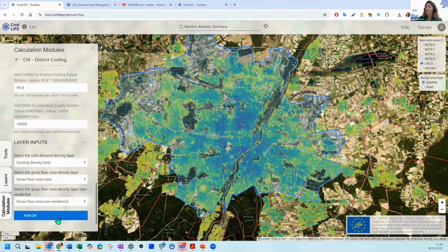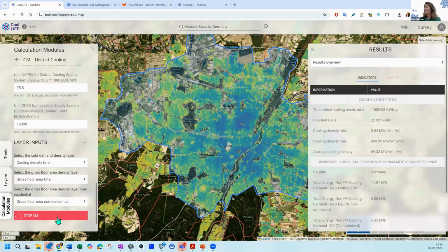Of course, what happens is that the higher the electricity price, the less convenient will be individual cooling supply, and the more convenient will be a centralized cooling network. The higher the number of cooling days, or the higher or lower the COP of the two systems, it will change significantly which areas are considered feasible for a district cooling. Let's have a look. I choose the cooling density total by default.